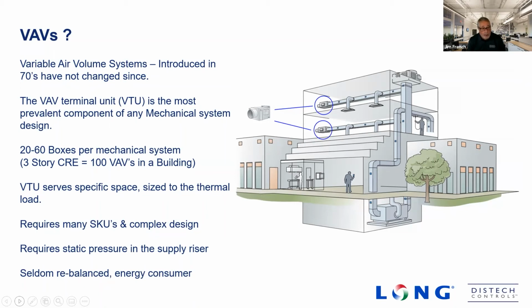anywhere from 20 to 60 boxes can be installed on a single air handler. Often there's buildings with multiple VAVs that include hundreds or even thousands of VAV terminal units. And each one of those is specifically sized for the space that it serves and the thermal load that's within. And so that requires a whole bunch of different sizes of terminal units. And it's a very complex design process for mechanical engineers to put these designs together because of the limitations of some of these terminal units we'll describe for you in just a second.